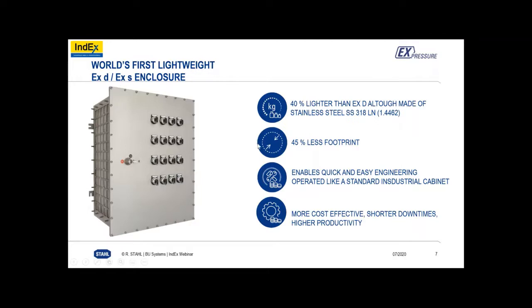Because we can use a wall thickness of only 2 millimeters, this makes it extremely lightweight and very spacious for an Ex d solution. That means we have thin walls and a lightweight enclosure. We have no additional wall mounting frame in the conventional meaning, and you can have only one large cabinet instead of a combination of several Ex d enclosures. That also means less footprint, up to 45% less, and it saves space. This makes the machinery and the system design more compact.